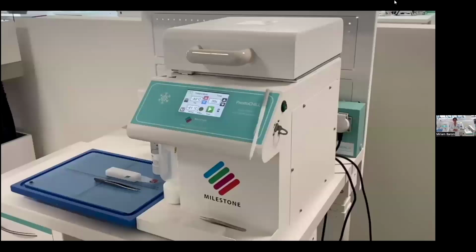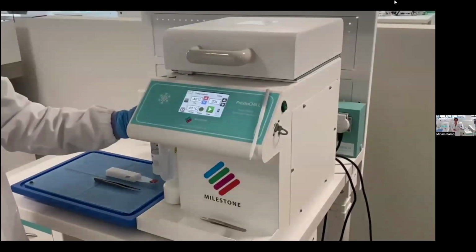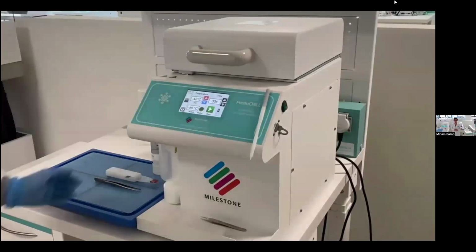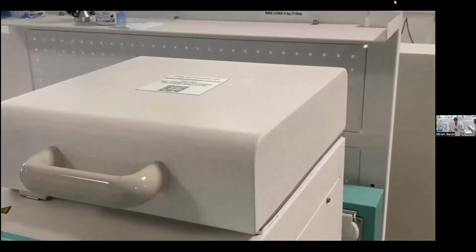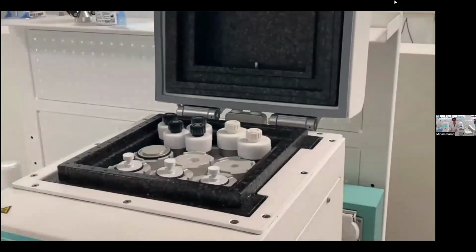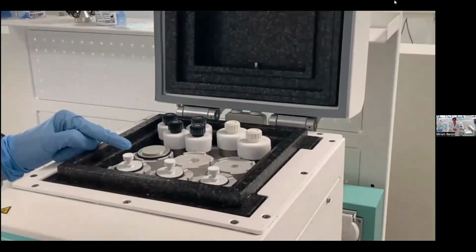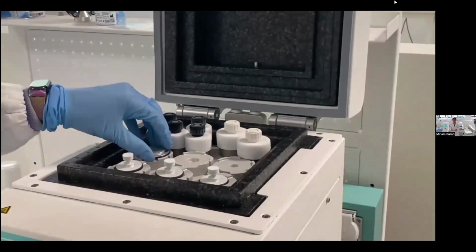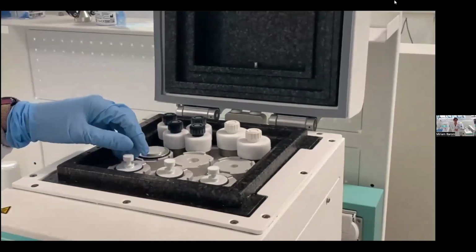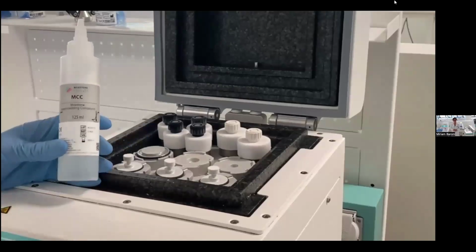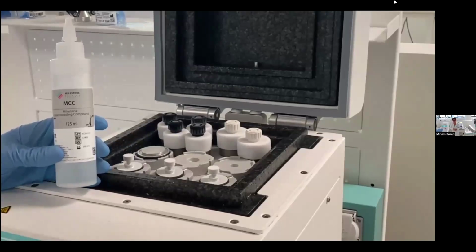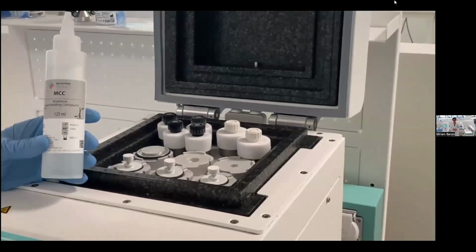Now, I will show you another short video that helped me show you our method to freeze a specimen. To improve the freezing quality, we have developed a new device called PrestoChill. This device has a working area with 6 metal molds at -40 degrees and allows us to freeze the sample with a phase down technique, like the procedure with the paraffin. This allows me to use a medium that is more liquid than a conventional medium.